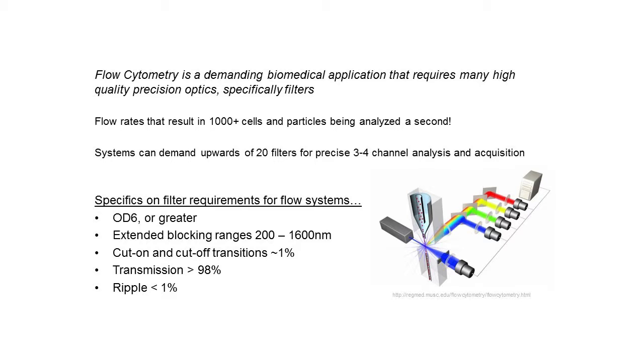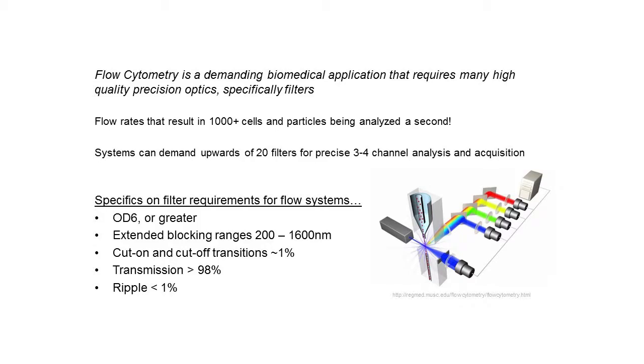Over 20 filters can be used in some of these systems in a three to four channel type of system. These filters are typically extremely highly specified on the OD6 or greater. Extended blocking ranges covering 200 to 1600 nanometers due to the fact that there are multiple channels and multiple excitation wavelengths. And the cut-on and cut-off transitions are roughly on the order of one percent or less. Transmission is greater than 98 percent. And your ripple needs to be extremely flat. It has to be on the order of one percent across the bandwidth.